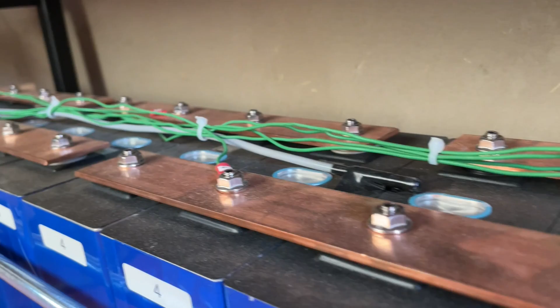There are BMS leads on every single one of the leads that we've labeled, and those run into our BMS. So our BMS monitors voltage, over voltage, under voltage, temperatures, and limits your amps, all of that stuff. It also has a shunt which monitors power coming in and out to give you an accurate assessment of your state of charge, in other words, how much percent is left in your battery.